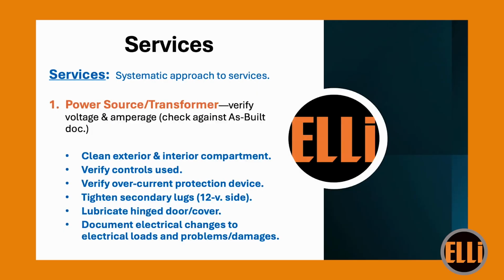Let's move on. So we've got verify controls used. I wrote that down as a means for quick inspection and make sure that your control modules are functioning properly. Okay, you can do quick tests on that to see if the system turns on and off, but you want to make sure each visit, if in most cases, maintenance visits occur once a year.